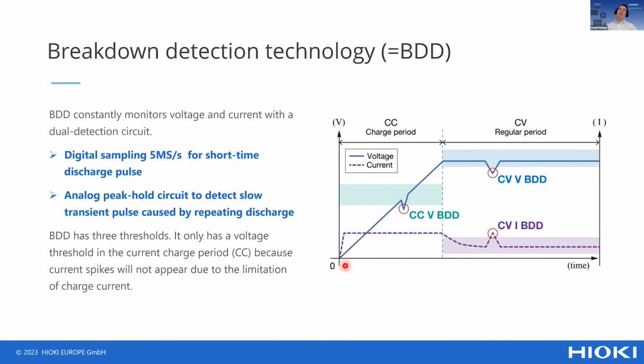So what happens in the process of testing with an insulation resistance tester? First, we have the charge period. A charge current of 50 milliamps is injected into the battery cell. Due to the limitation of that charge current, in this part it's only possible to monitor voltage. While in the regular period, once it's charged, you also have the possibility to capture voltage and current. We have three colored areas in here. These two areas are for detecting the voltage. This area is for detecting the current. And this is something the user of the device can set as a threshold by themselves.